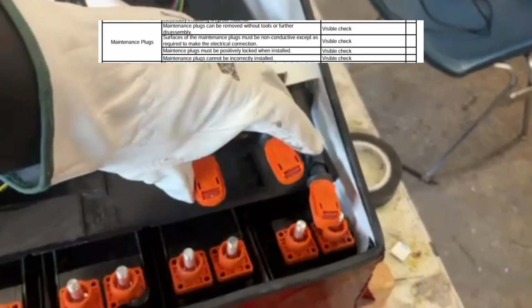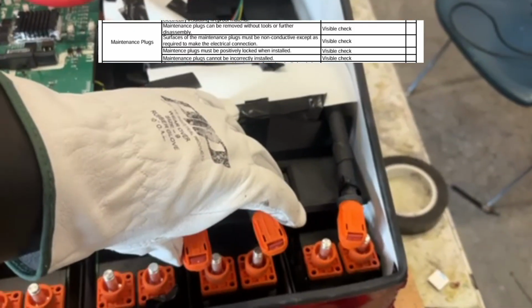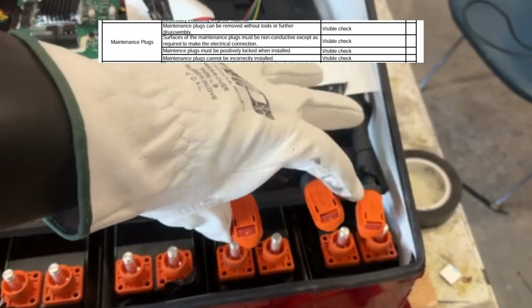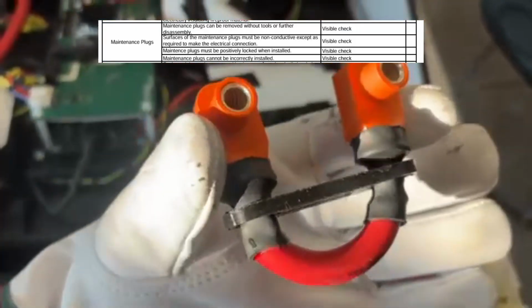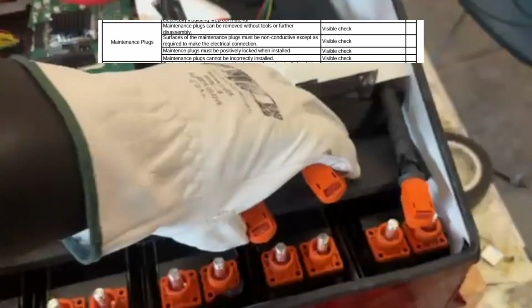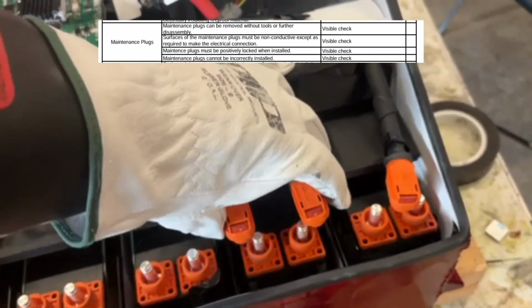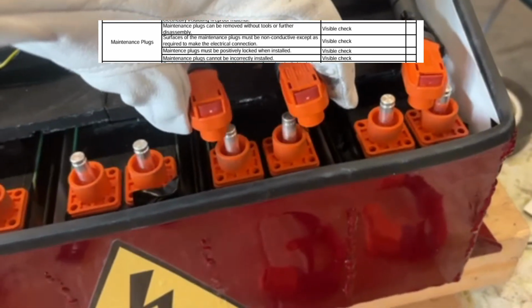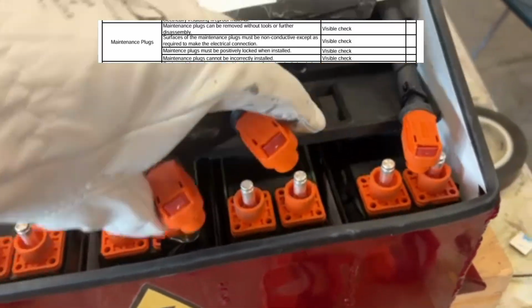For the rest of our maintenance plugs, they're supposed to be installed like this. They should not be installed shorting these 2 terminals, and they can't, because this plastic 3D printed piece holds these rad lock plugs apart so that they're too long to fit on here like this. Even if I press them together, I can't do anything.